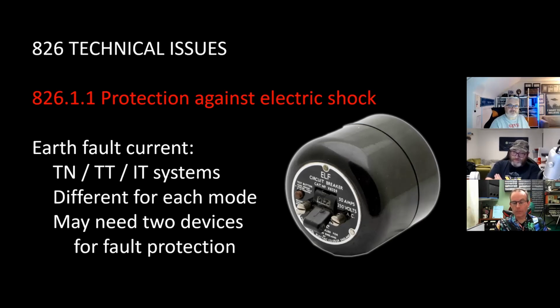Sad bit of knowledge. So the earthing system could be different for each mode, and because of this, you might need two devices for fault protection. Now, it actually says this in section 826.1.1. In theory, you could have two separate devices, or more likely, it's going to be a single device with two types of protection in it. I don't think having two separate devices is particularly valid - you'll have to consider each mode when doing your selection and erection, and select a single device that achieves compliance with both.